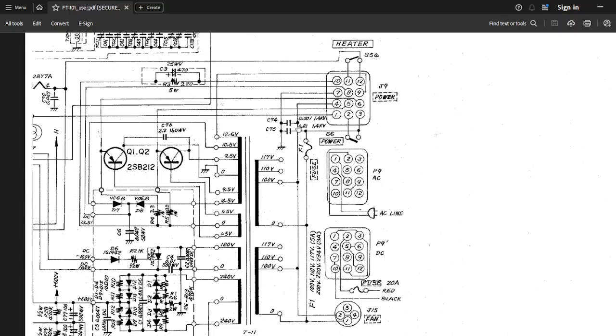What I'm suspecting is that this capacitor, and possibly this one to a certain degree too, is getting leaky—meaning it's passing voltage it's not supposed to. There's going to be some voltage across it just because it's a capacitor, but due to its capacitance value, not very much actually gets through to ground. The 60 hertz doesn't pass through it very well, but higher frequencies can pass through easier. So if you have RF coming in through the power line, it's basically shunted to ground, keeping it from getting into the radio. It's kind of a high pass filter type capacitor.